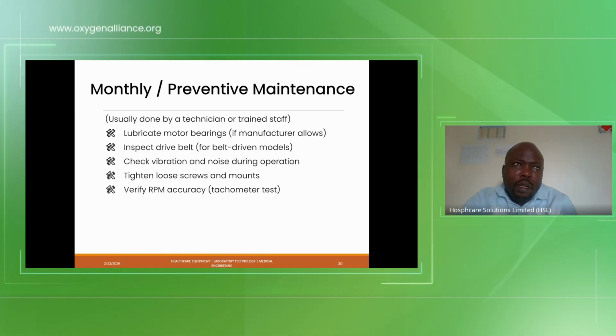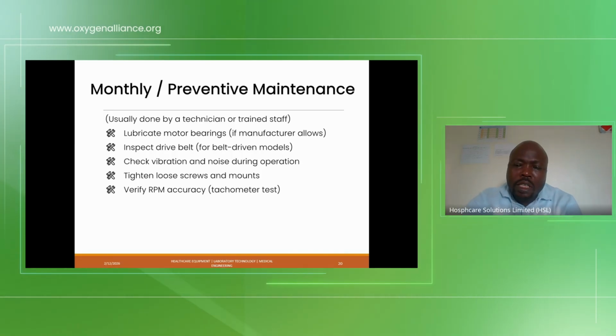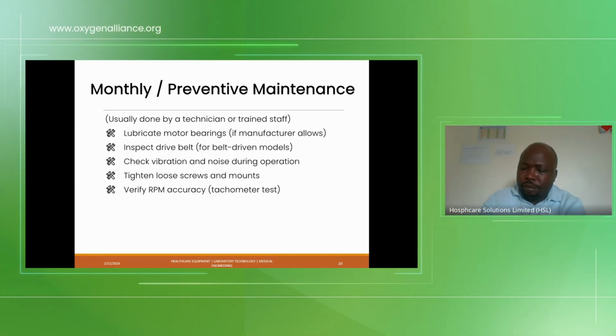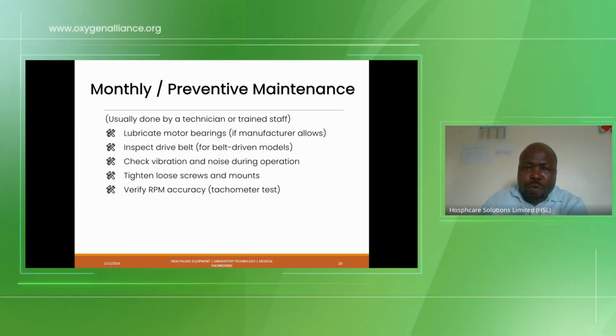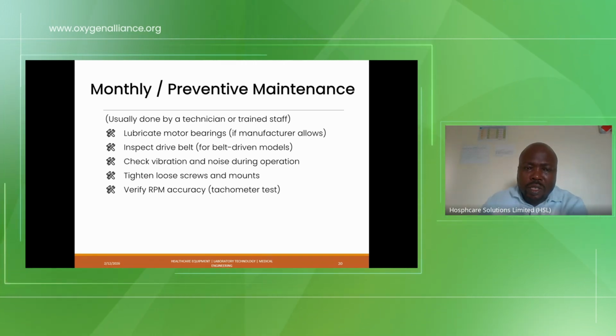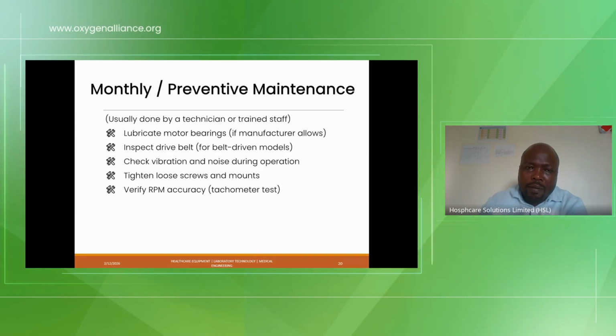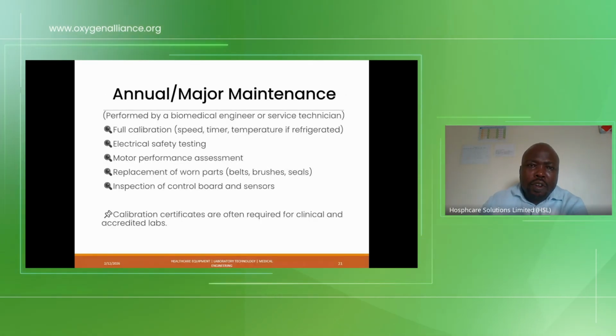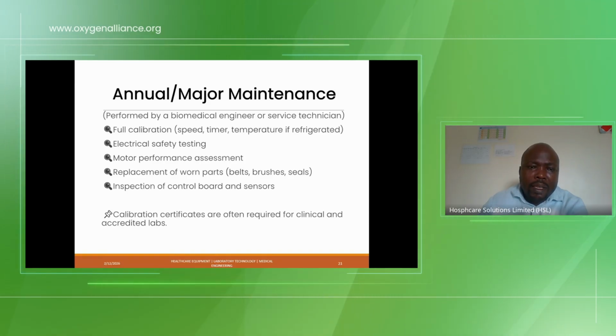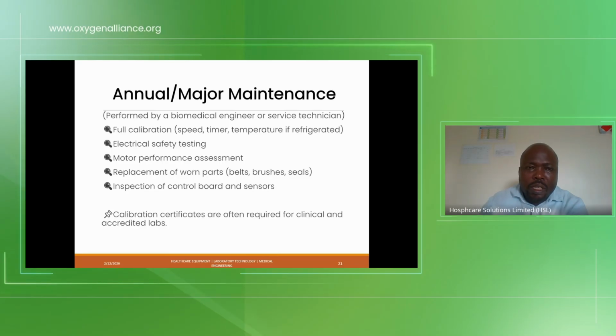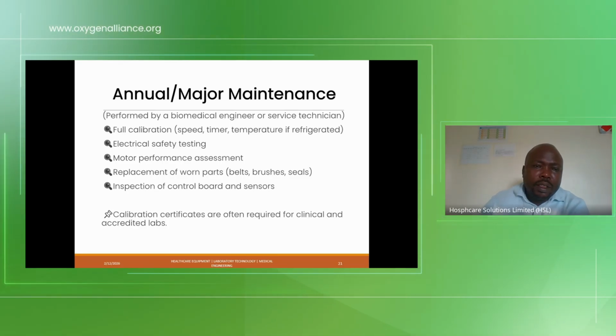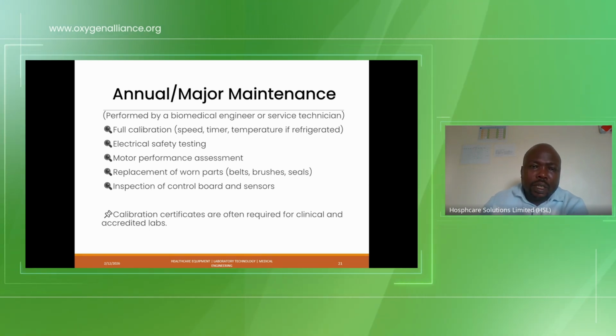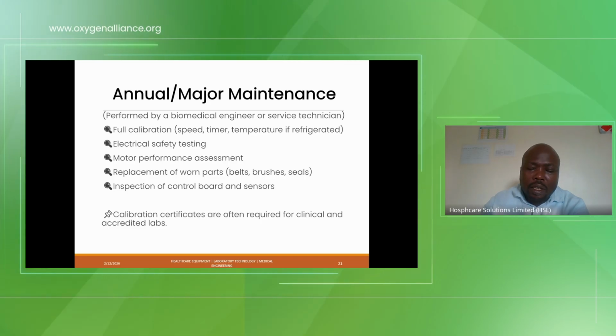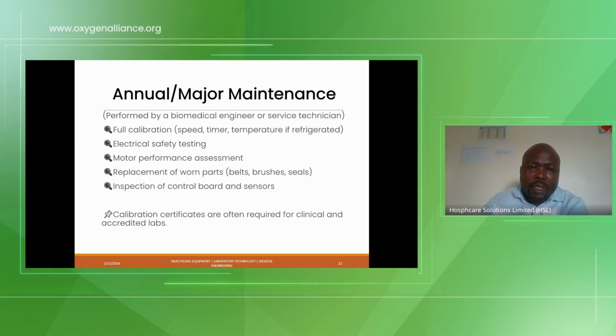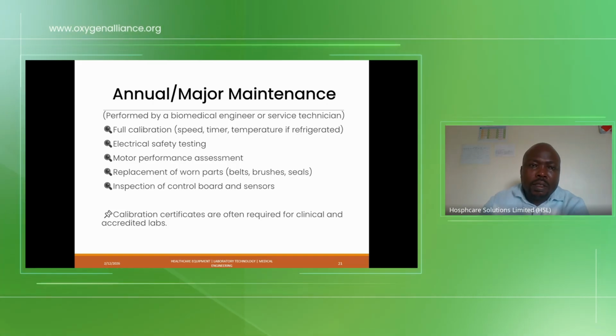Yeah, I've said that a refrigerated centrifuge is applied in special case scenarios where the specimen is required to be kept at very regulated low temperatures. So that's why my colleague from Nigeria rarely came across such a machine. It's applied in rare case scenarios. So just like normal refrigerated appliances, you need to check the refrigerant for leakages, you check the timer, then you blow the dust from the filter side. And also check the sensors, the heat temperature sensors. Okay, so that is the normal maintenance checkup on the refrigerated centrifuge machine.